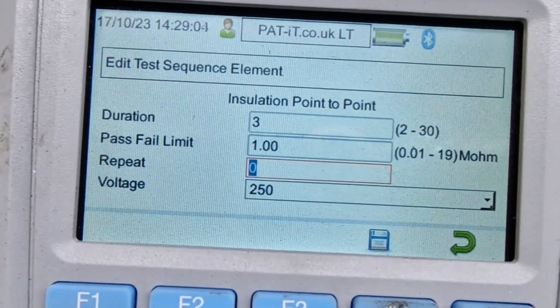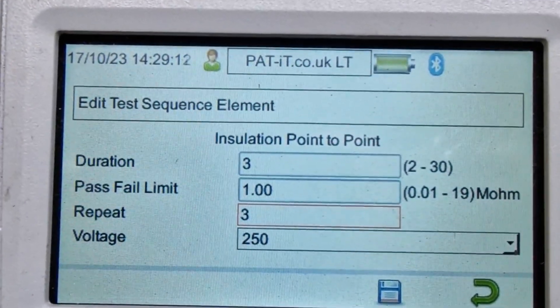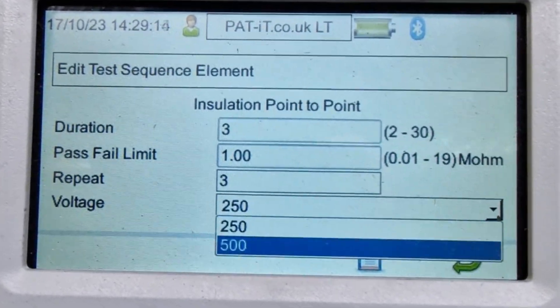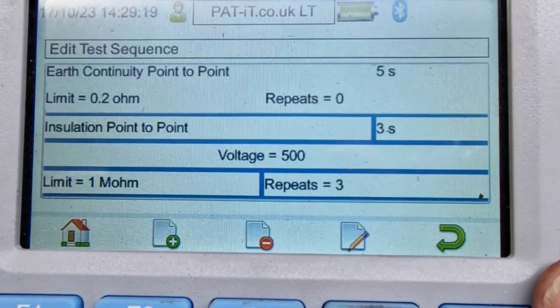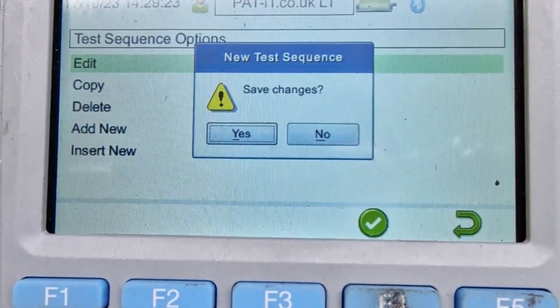Repeat. As it's 3 phase, it's already doing one test — we have four there, so we want it to repeat three other times. Test voltage at 500 volts. And F4 to accept. That's that — so return F5. Doing save.